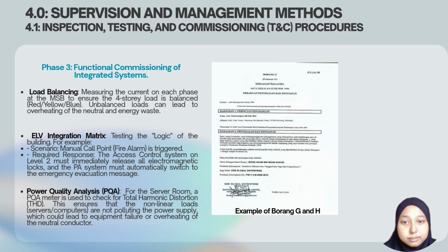Next is the ELV integration matrix, testing the logic of the building. For example, the scenario is a manual call point or fire alarm is triggered. The required response is the access control system on level 2 must immediately release all electromagnetic locks, and the PA system must automatically switch to the emergency evacuation message. Lastly is power quality analysis (PQA). For the server room, a PQA meter is used to check for total harmonic distortion (THD). This ensures that the non-linear loads, servers or computers, are not polluting the power supply, which could lead to equipment failure or overheating of the neutral conductor.